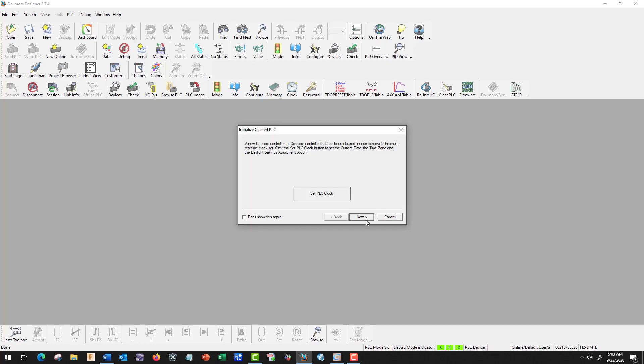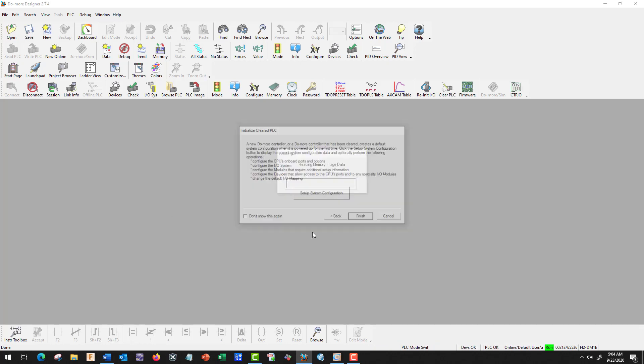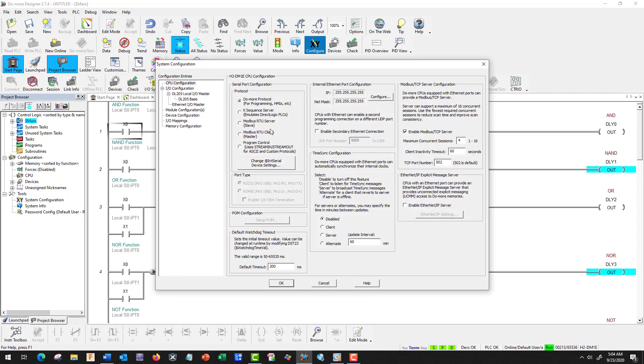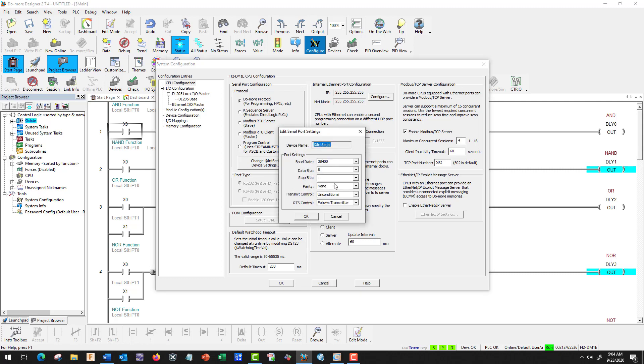Good, so we're going to set our time and everything. There's some functions here, that's okay. What we're interested in here is going over to Configure. In order to talk to our OIT, we have to be in the Do More protocol, and we're going to change our settings. It should be 38,400 baud rate. If not, it will not communicate. Just leave everything else the same: should be 8-1, unconditional follow transmitter.